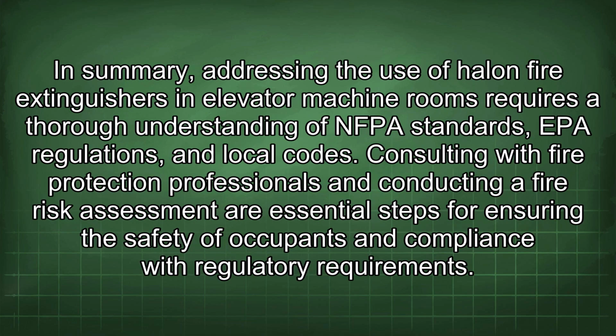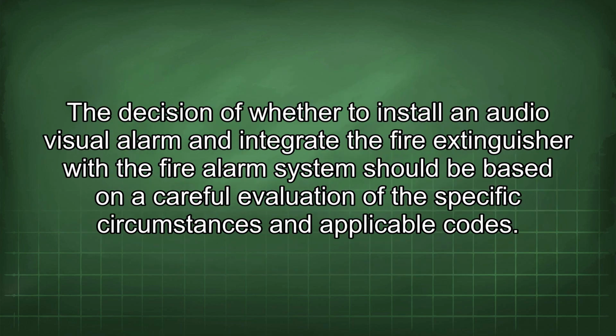In summary, addressing the use of Halon fire extinguishers in elevator machine rooms requires a thorough understanding of NFPA standards, EPA regulations, and local codes. Consulting with fire protection professionals and conducting a fire risk assessment are essential steps for ensuring the safety of occupants and compliance with regulatory requirements. The decision of whether to install an audiovisual alarm and integrate the fire extinguisher with the fire alarm system should be based on a careful evaluation of the specific circumstances and applicable codes.